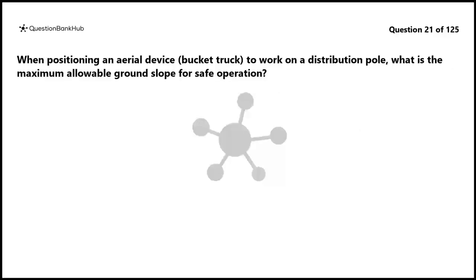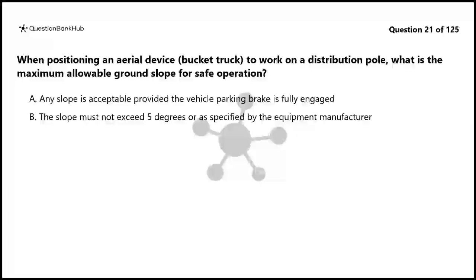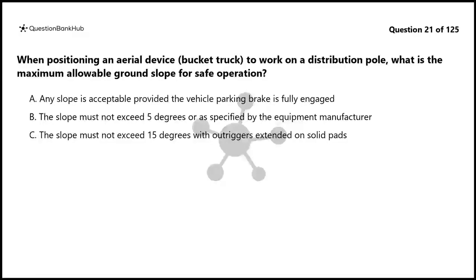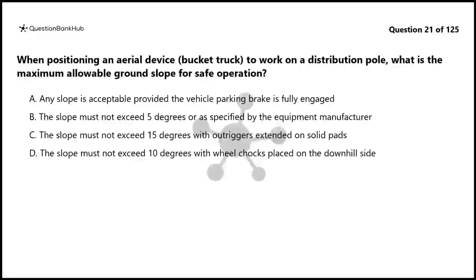Question 21. When positioning an aerial device, bucket truck, to work on a distribution pole, what is the maximum allowable ground slope for safe operation? A. Any slope is acceptable provided the vehicle parking brake is fully engaged. B. The slope must not exceed 5 degrees or as specified by the equipment manufacturer. C. The slope must not exceed 15 degrees with outriggers extended on solid pads. D. The slope must not exceed 10 degrees with wheel chocks placed on the downhill side.